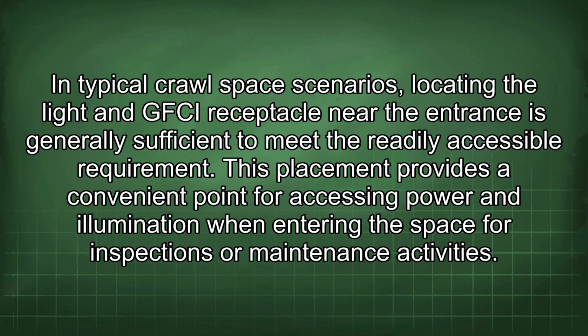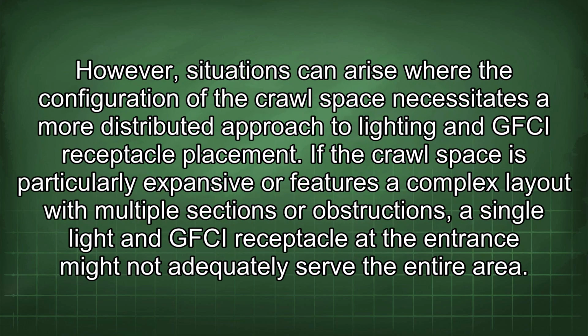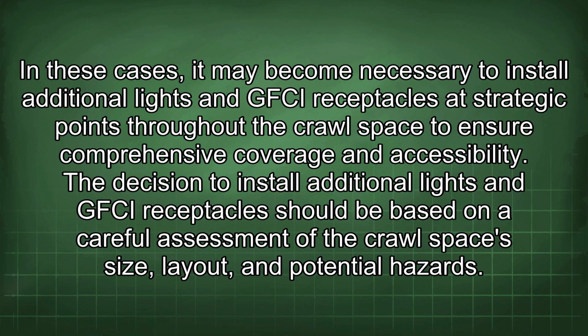In typical crawlspace scenarios, locating the light and GFCI receptacle near the entrance is generally sufficient to meet the readily accessible requirement. This placement provides a convenient point for accessing power and illumination when entering the space for inspections or maintenance activities. However, situations can arise where the configuration of the crawl space necessitates a more distributed approach to lighting and GFCI receptacle placement. If the crawl space is particularly expansive or features a complex layout with multiple sections or obstructions, a single light and GFCI receptacle at the entrance might not adequately serve the entire area. In these cases, it may become necessary to install additional lights and GFCI receptacles at strategic points throughout the crawl space to ensure comprehensive coverage and accessibility.